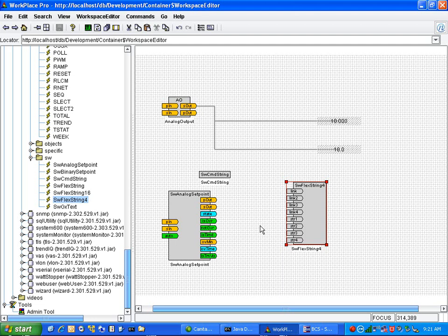It's pretty impressive. It's a lot of programming to do, but I had Steve make these, and these flex strings link to the description field of the logs, and I can set up some other blocks where I can make the room numbers a right-clickable changeable item. When you change your room number, you're actually changing the log description. It links right up to the log descriptions and changes everything you would need to change if you made a room number change.